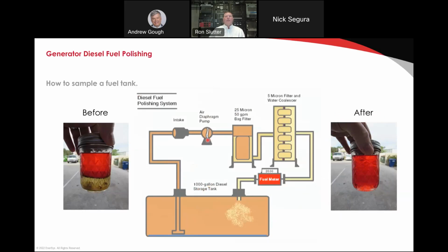So now let's say that we have our fuel sample, and we need to deal with the problems that we've identified in the tank. Here's our sample. Doesn't look very good. We need to get it to look like this sample here on the right. This is called polishing. So what we do is we're removing the fuel from the bottom of the tank where we have this water layer. We're pulling it out of the system and running it through this series of filters and putting it back into the tank when it's clean. And so we're trying to stir it up and eliminate the fuel that is contaminated.